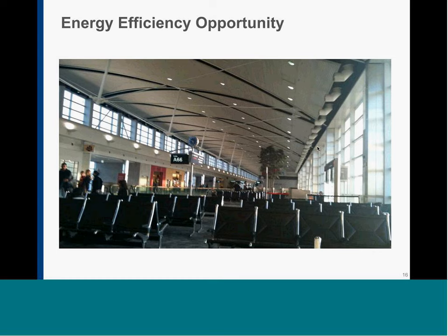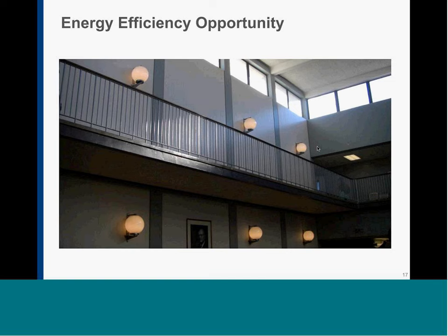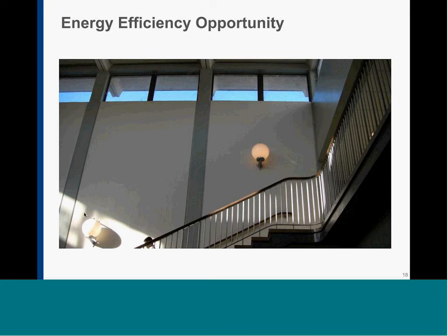Of course, I don't have to travel the country to do that. Here are buildings on our campus. This, by the way, has incandescent lamps. You get the beautiful design with the clerestories illuminating this atrium, and all the incandescent lights are on. It's like noontime, and I couldn't resist this one, this luminaire down at the bottom left. It's on, and it's on in sunlight. You cannot even see that it is on. So these are opportunities that we really need to address, and they are widespread: cases where, with plenty of daylight, we have all of the electric lights on.